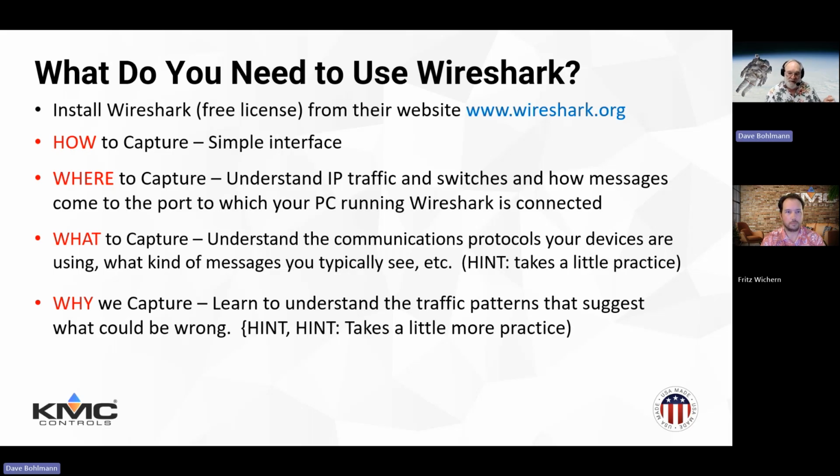So if you're trying to see the messages between devices, a lot of times you have to run Wireshark on the other device, like let's say Commander or Total Control or whatever. That way you'll be able to see all the messages. If you don't, you'll just see the broadcast and you'll only get part of what you're maybe looking for.